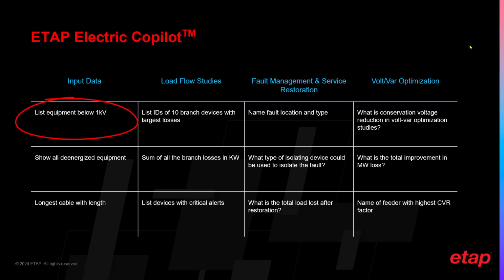Let's say you have special arc flash solutions at 15 kV and above, and you want to see the equipment included in that scenario. You can simply query your Copilot to show you the equipment which would be included. Maybe you want to show all de-energized equipment, looking at maintenance, what's out. You want to look at the one-line determined based on switching configuration, breaker configuration, different statuses of equipment. You want to show any equipment that's de-energized in your project, you can simply ask. You want to know what the longest cable is and its length. So we're looking at input data from this perspective.